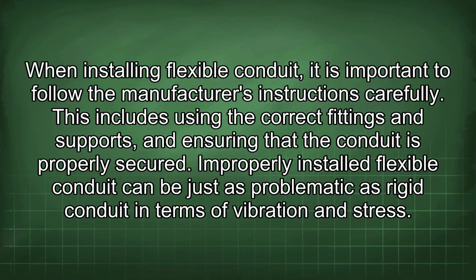When installing flexible conduit, it is important to follow the manufacturer's instructions carefully. This includes using the correct fittings and supports, and ensuring that the conduit is properly secured. Improperly installed flexible conduit can be just as problematic as rigid conduit in terms of vibration and stress.